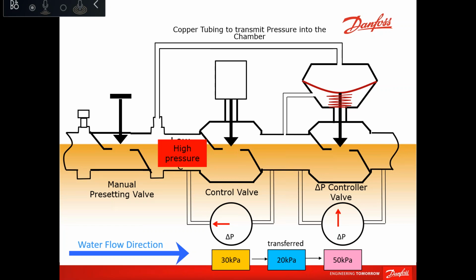So yes, but I only see this smaller flow on a telephone room flow rate or electrical room on the floor level. You can see a couple of units, but usually the minimum setting I was able to see was like 20%, but on DN15. Then I changed it to DN10 low flow, and the setting became 52%. That is how I made it on the safe side, because I wanted to leave some safety on both sides, on the lower and higher end of the setting range.